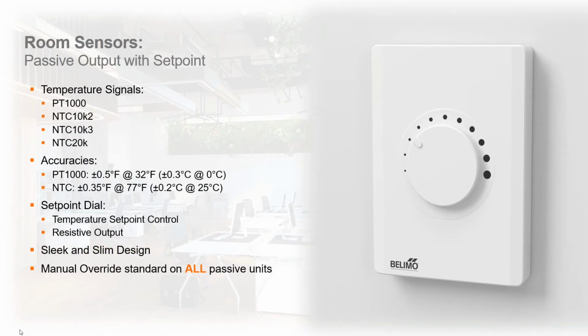All right, so jumping over to the next group here would be our Setpoint sensors. These are the exact same thing as the previous sensors I spoke about when it comes to design, accuracy, and the manual override as well, except of course these have an added temperature Setpoint dial. This Setpoint dial has a resistive output itself, so it gets wired into your BMS system, and your BMS system will be able to read that resistance output, and you can control based on however your application needs.